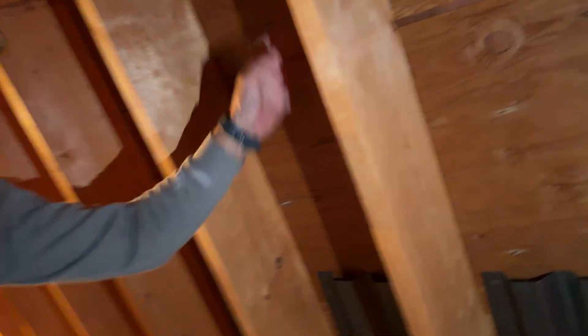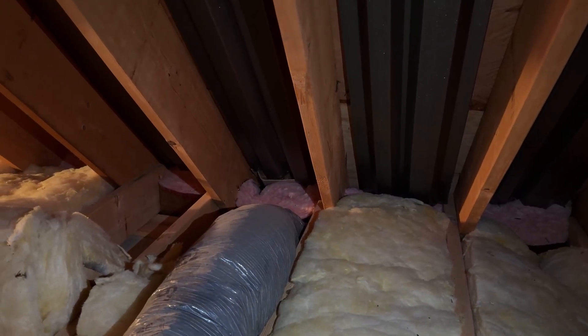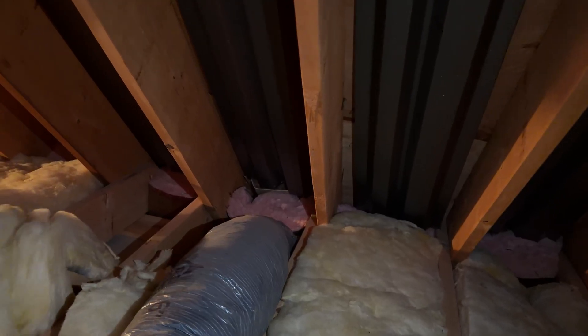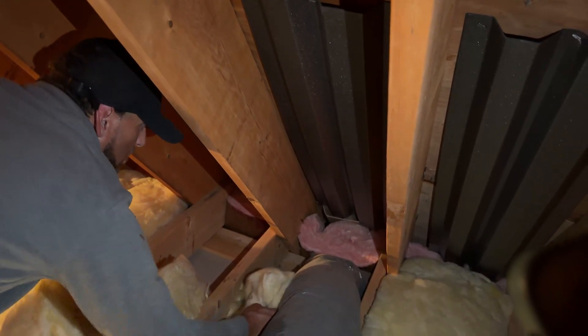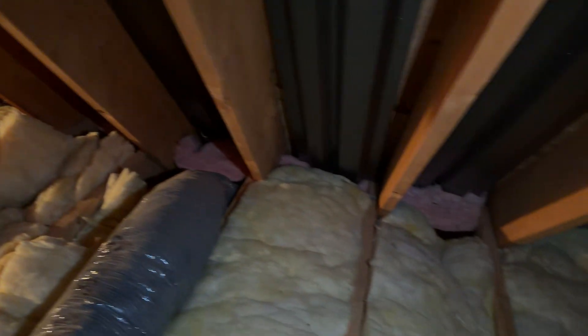A lot of those gaps over time — without adequate insulation — can cause moisture issues. The hot air and cold air collide in winter and you end up getting frost or moisture and condensation building up on the roof decking. Right now it's hot and dry so there's no visible effect up here, but underneath it means high energy bills from heat loss and central air. We make sure to always air seal all top plates, duct boots, and other penetrations.